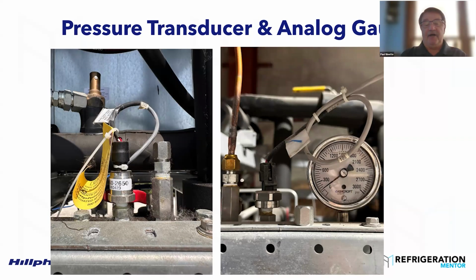All right, so once we verify, and it's way easier to verify all this to make sure your HP, your high pressure valve, and your gas bypass valve are moving before you put liquid in it. Because once you get liquid in it, then you're going to have to deal with the outcome of not being able to control your pressure. It doesn't take long once you get all this stuff done.